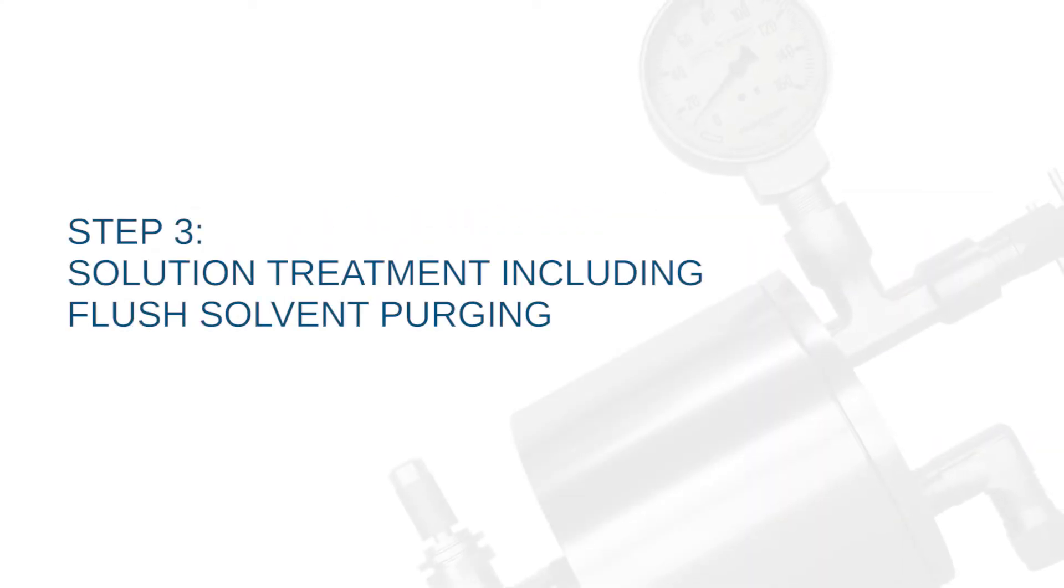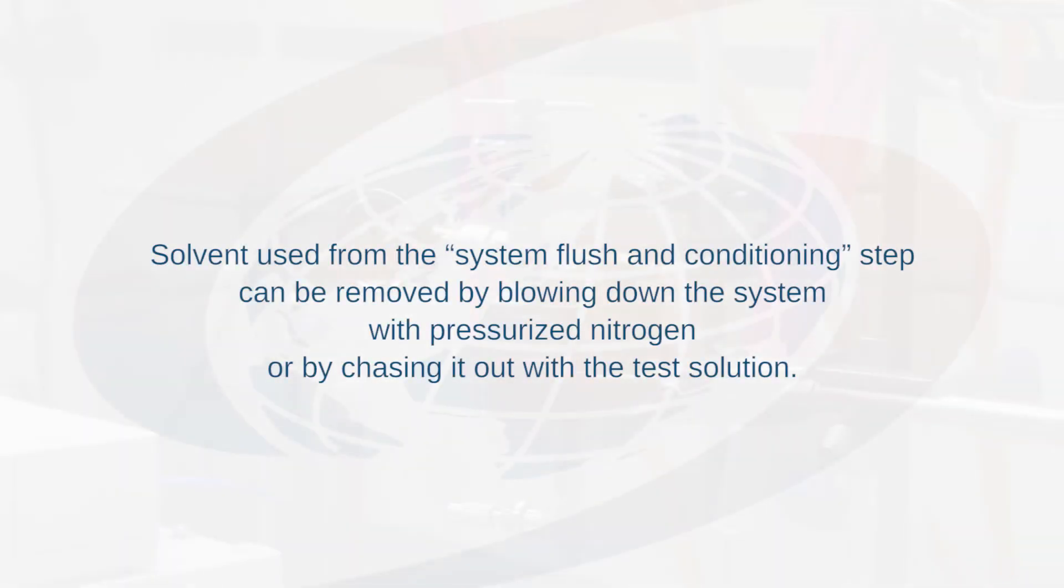Step 3: Solution treatment including flush solvent purging. Solvent used from the system flush and conditioning step can be removed by blowing down the system with pressurized nitrogen or by chasing it out with the test solution.